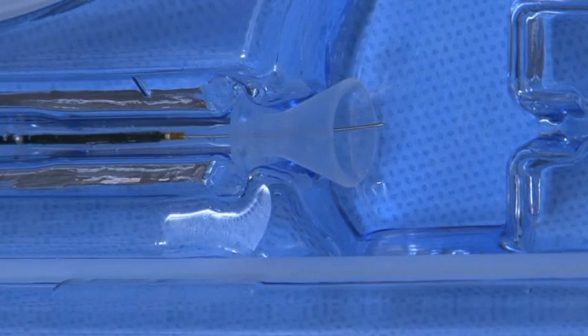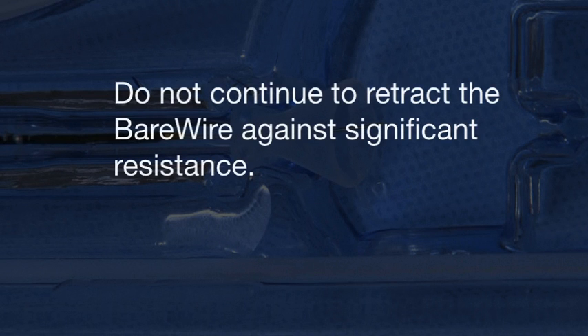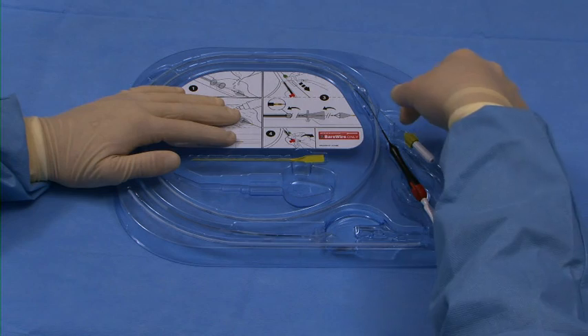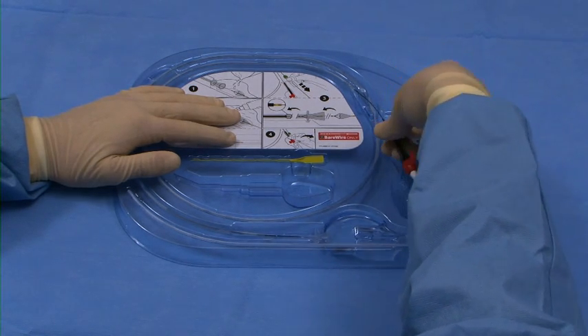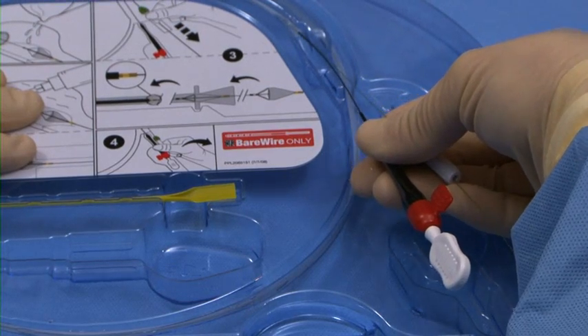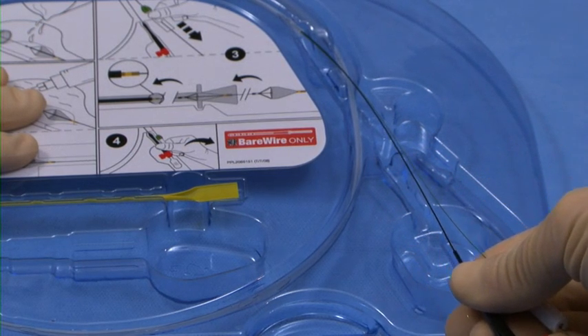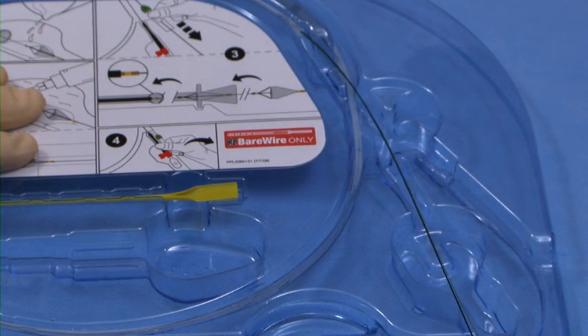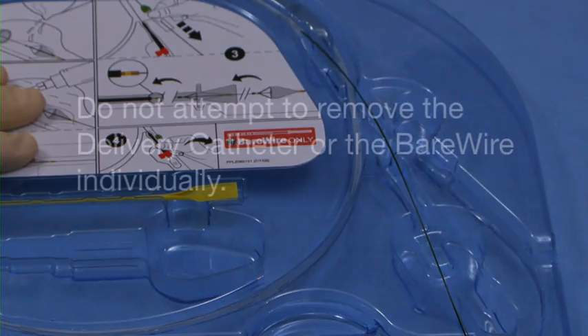The filtration element is fully loaded when the distal marker band is at or inside the end of the delivery catheter pod and a definite stop is felt. Do not continue to retract the bare wire against significant resistance. Grip the black handle on the delivery catheter and the torque device out of the tray together. Gently pull them together to remove the loaded delivery catheter and the bare wire from the tray. Do not attempt to remove the delivery catheter or the bare wire individually.